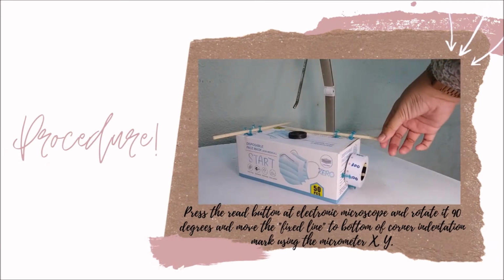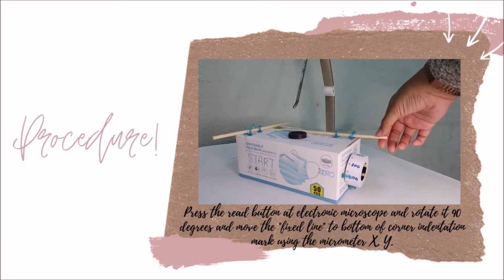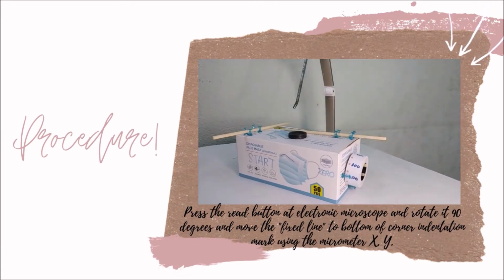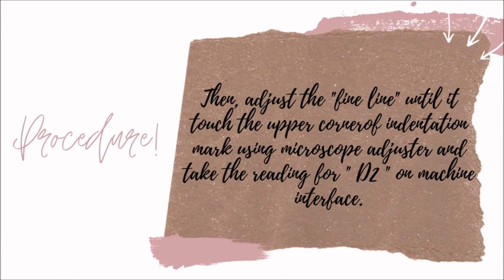the reading of D1. Press the read button on the electronic microscope and rotate it 90 degrees, and move the fixed line to the bottom corner of the indentation mark using the micrometer X and Y. Then adjust the fine line until it touches the upper corner of the indentation mark using the microscope adjuster and take the reading for D2 on the machine interface.